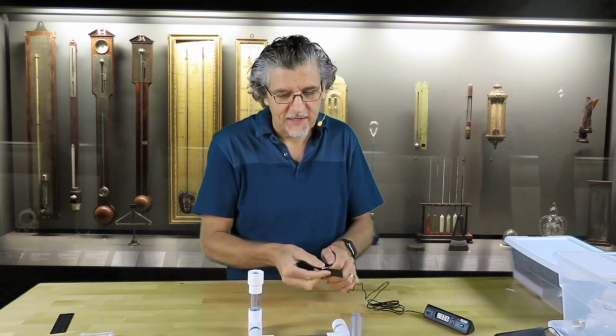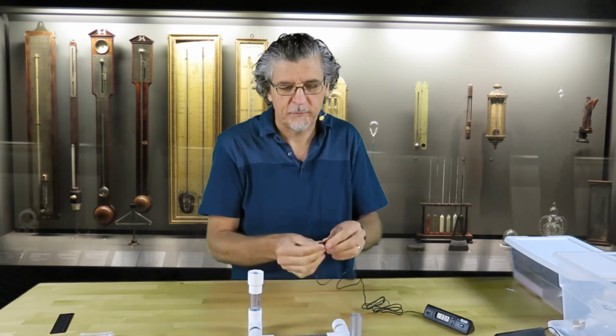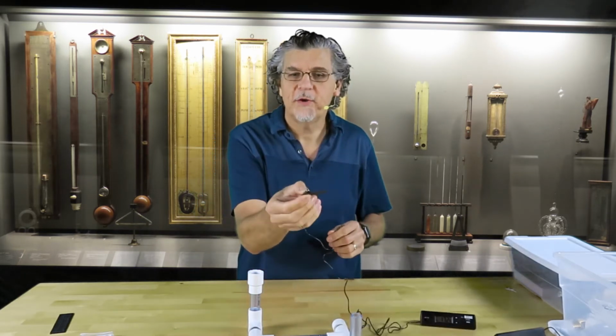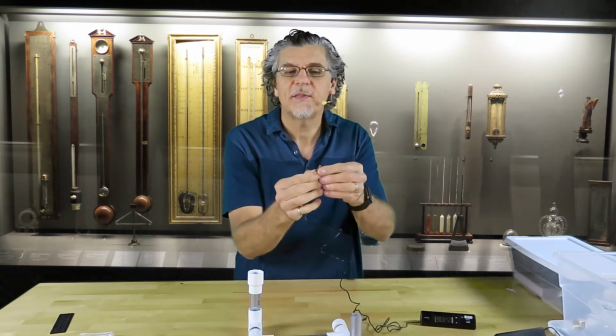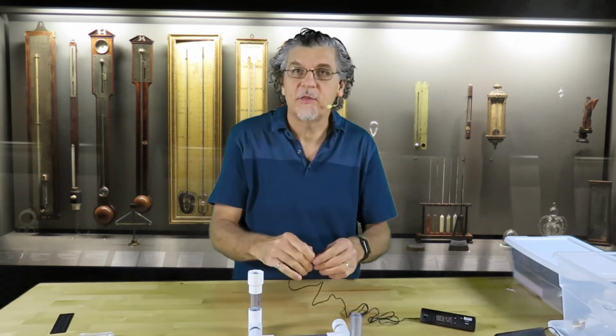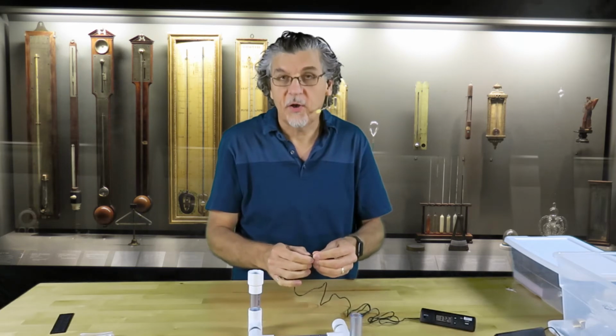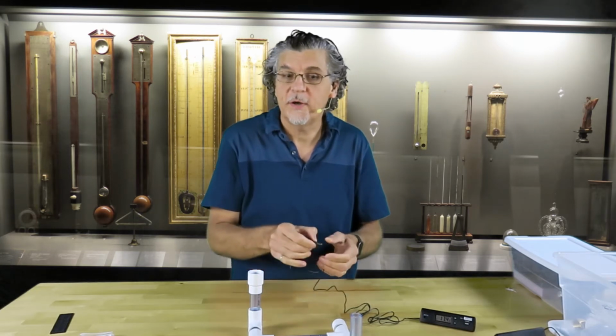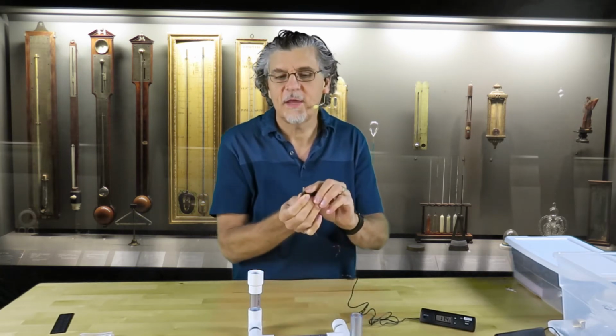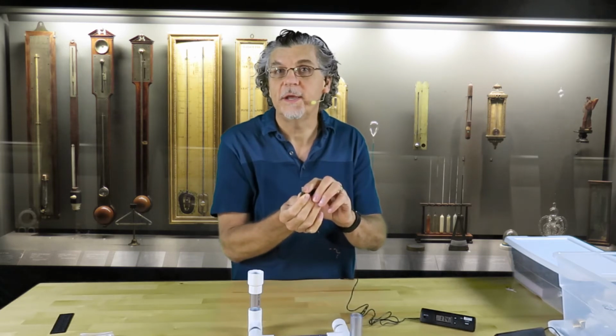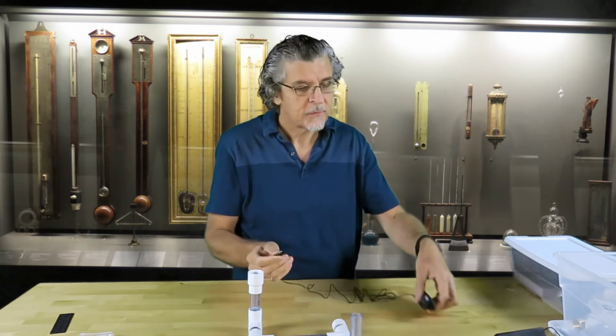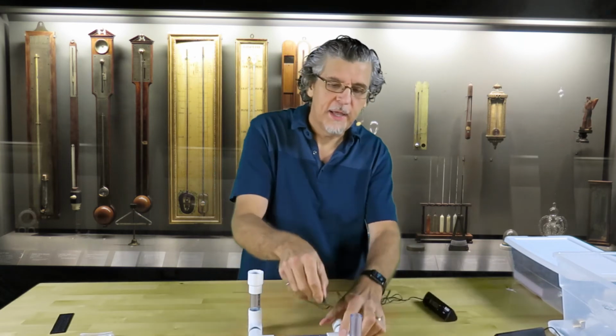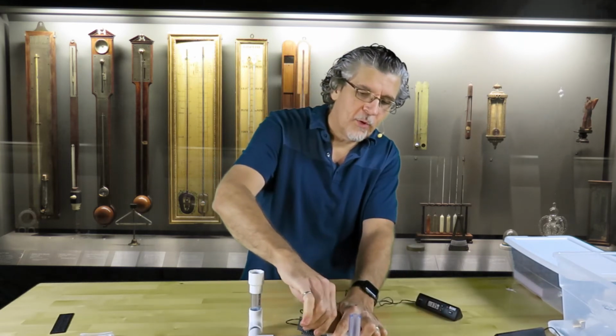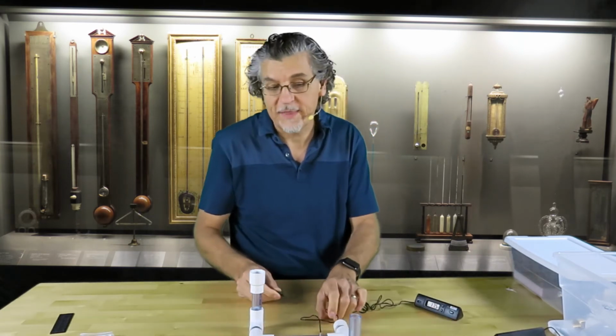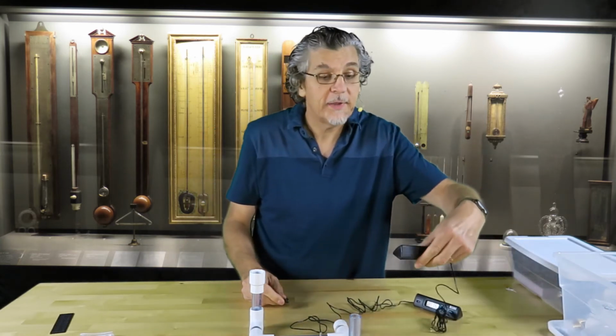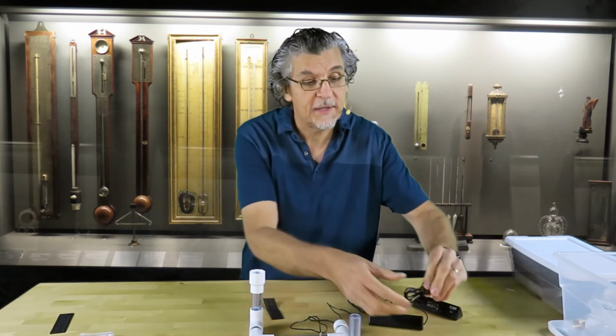If it's tight, you're going to want to take the little black strip, put it around your NTC sensor like this, and that is how you'll insert it. You don't need to insert it all the way. It only has to go in about halfway, just so that the sensor part is immersed in the liquid when we perform the calibration. So I'm going to begin with T1, and I'll put it into the first hole. And that was an easy one. That one was drilled with a sufficient diameter to make it easy.